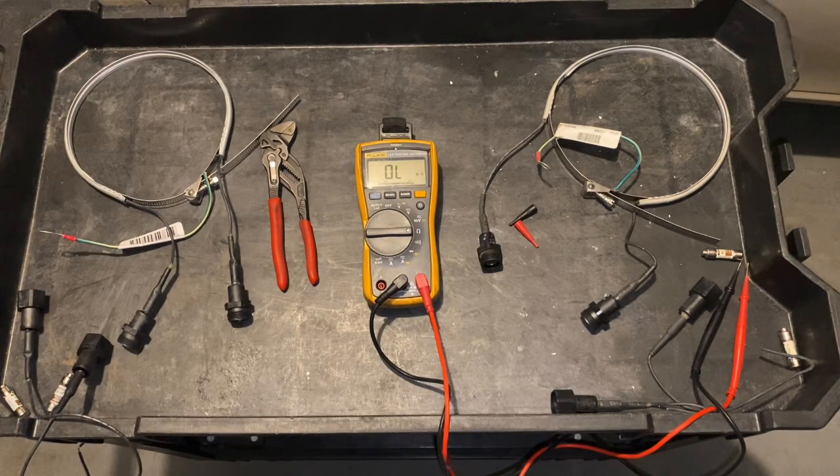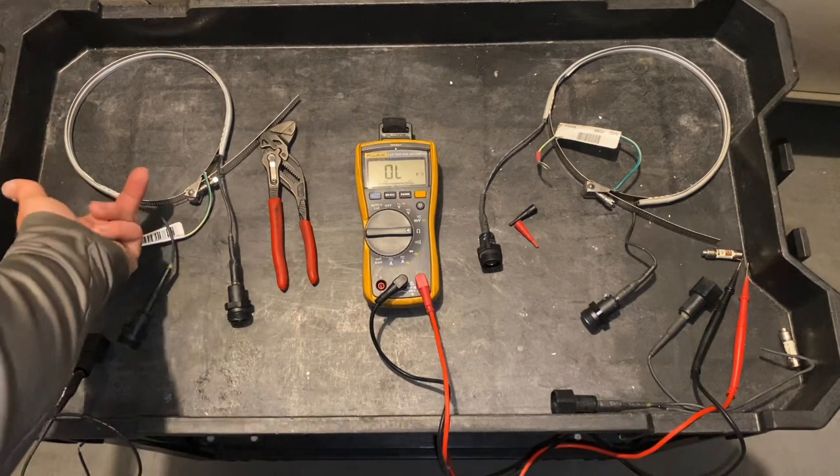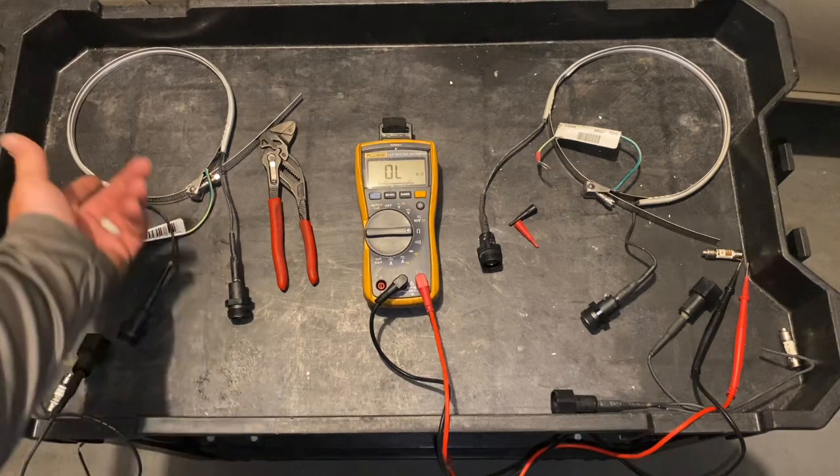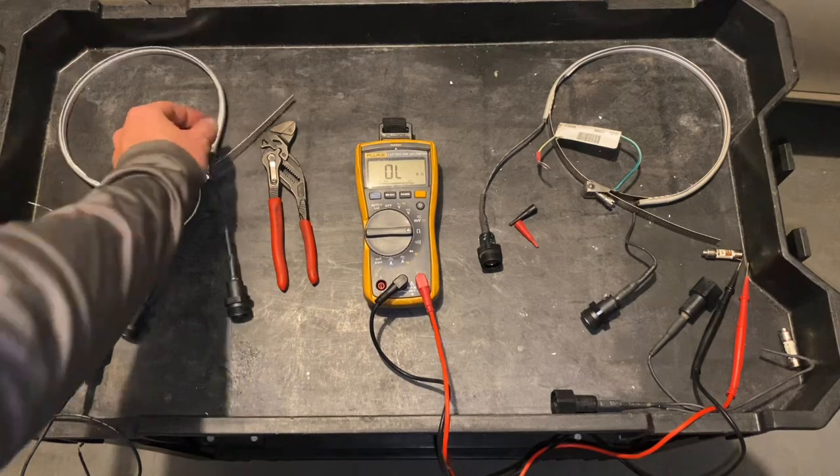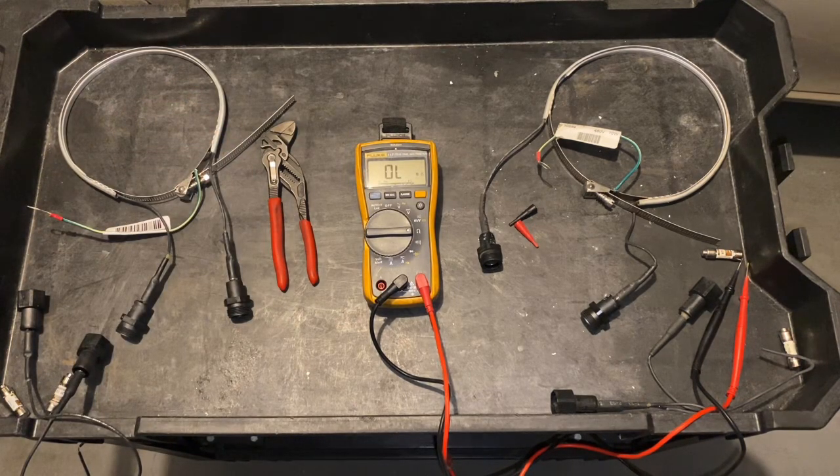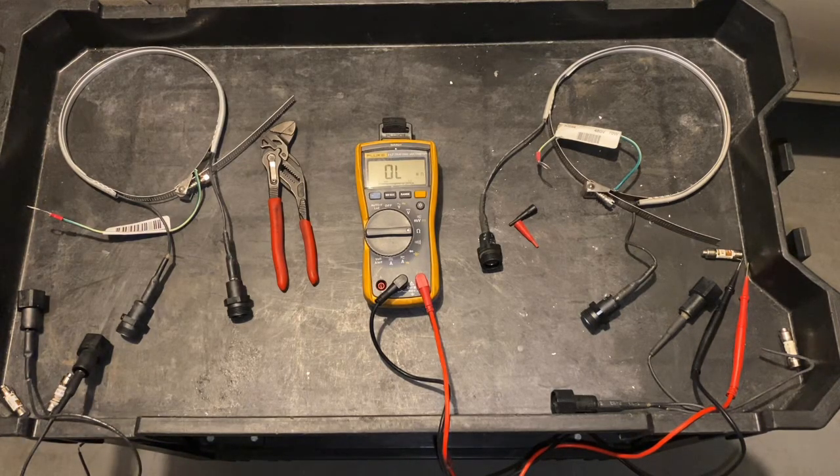Usually crankcase heaters are going to be wired in so when the compressor is off, the crankcase heater is on. So if you've got the compressor off, you can do a touch test and check it that way. If it's hot, especially compared to another compressor with a failed crankcase heater, you can compare things that way and know that that crankcase heater is working.